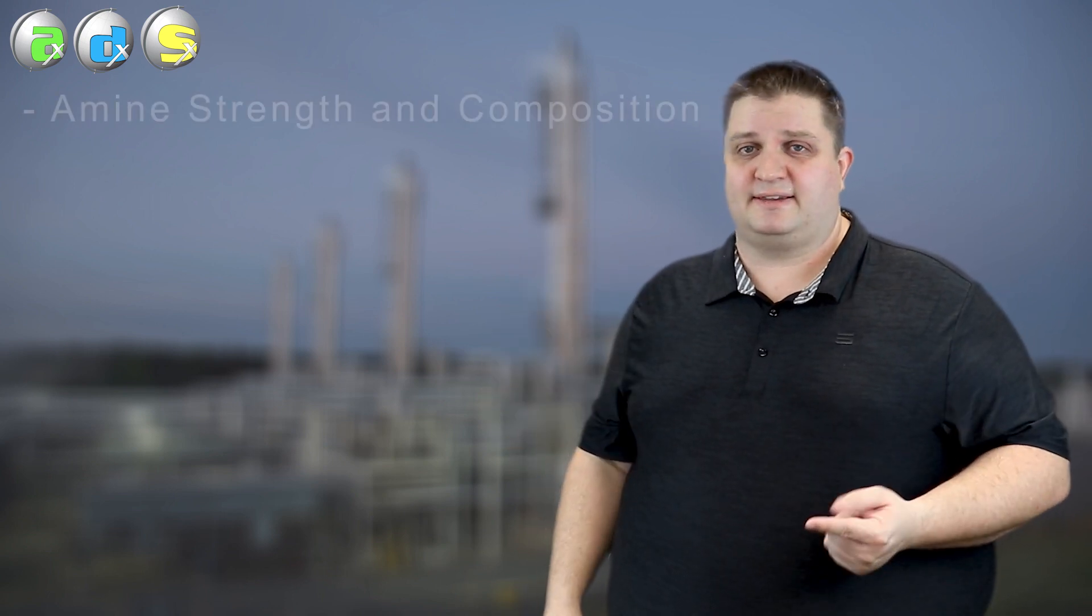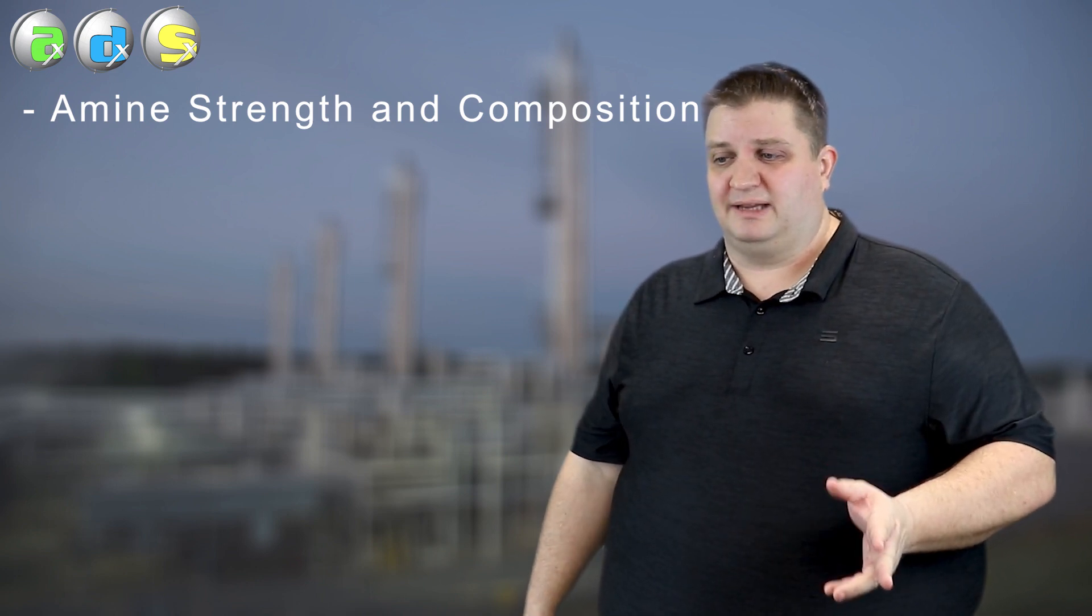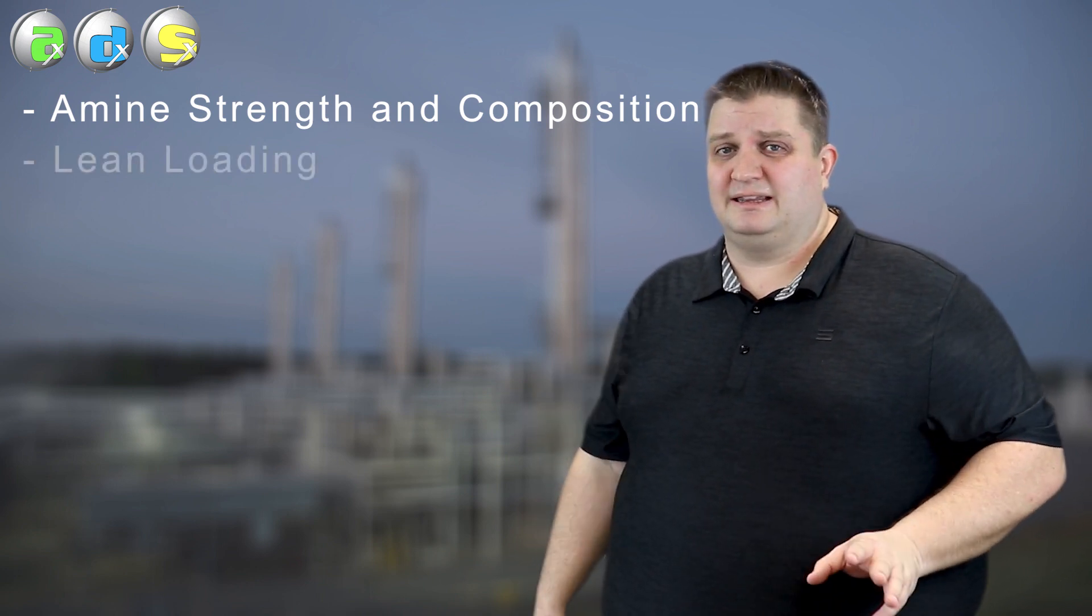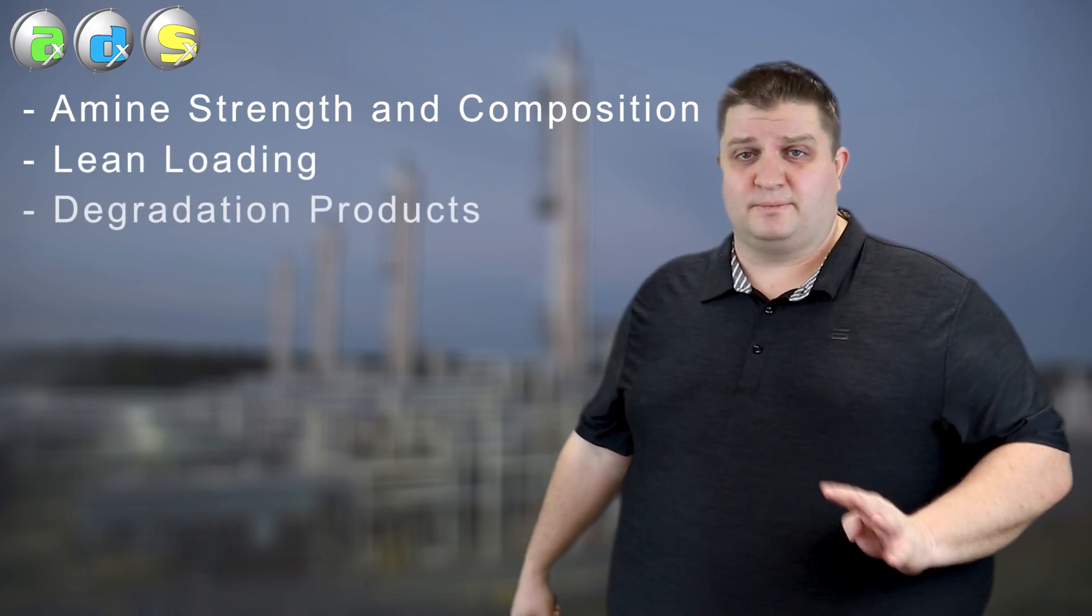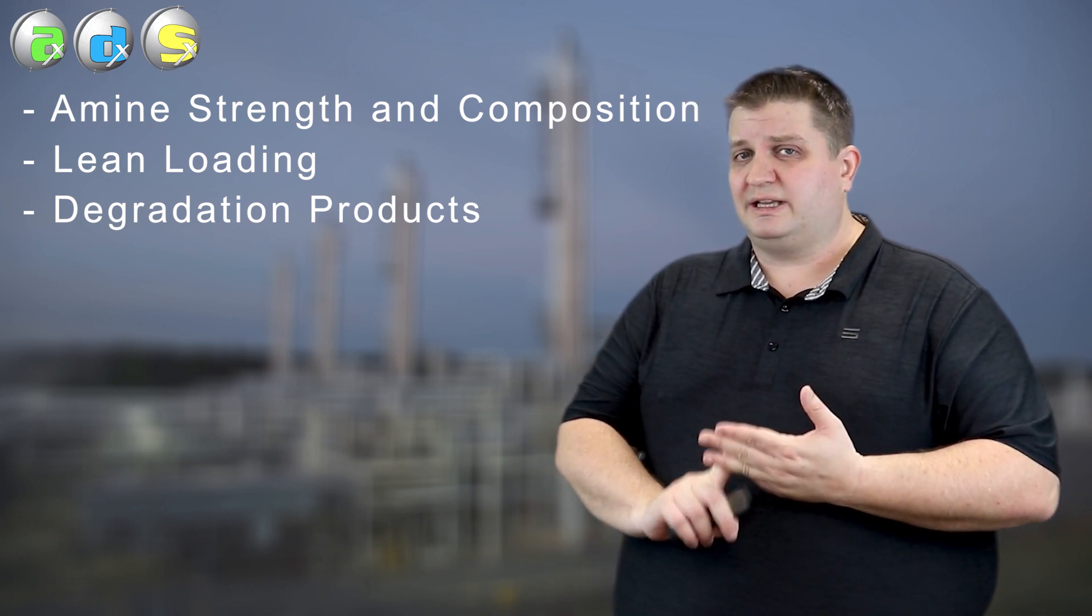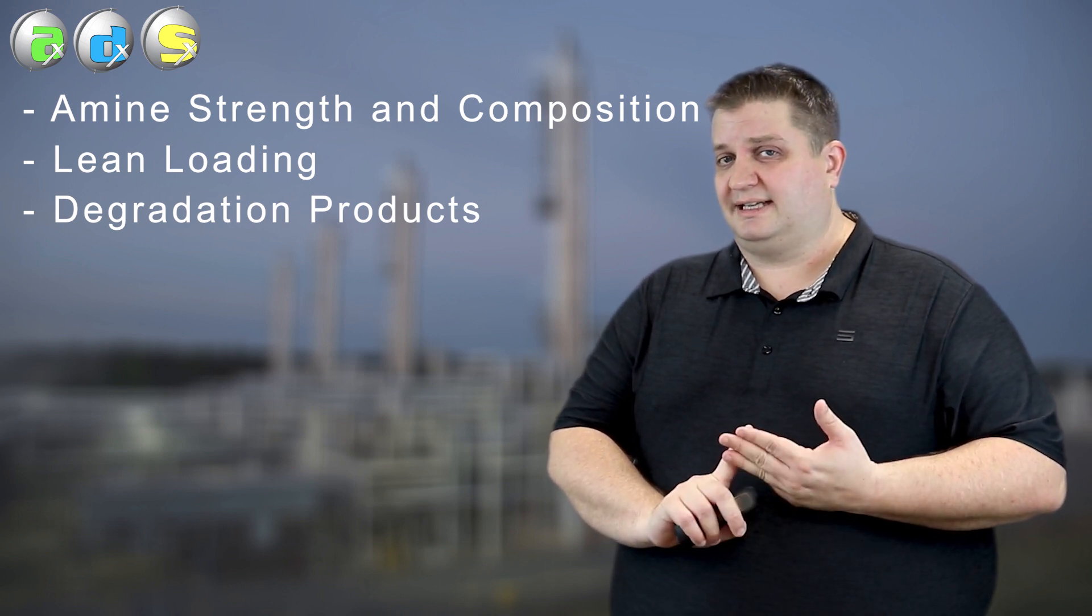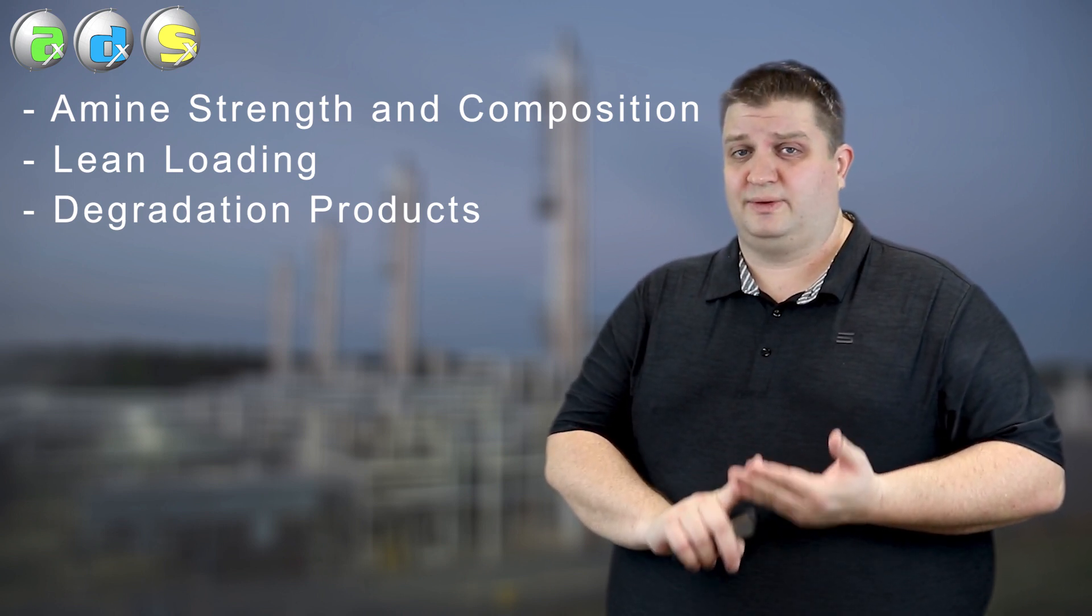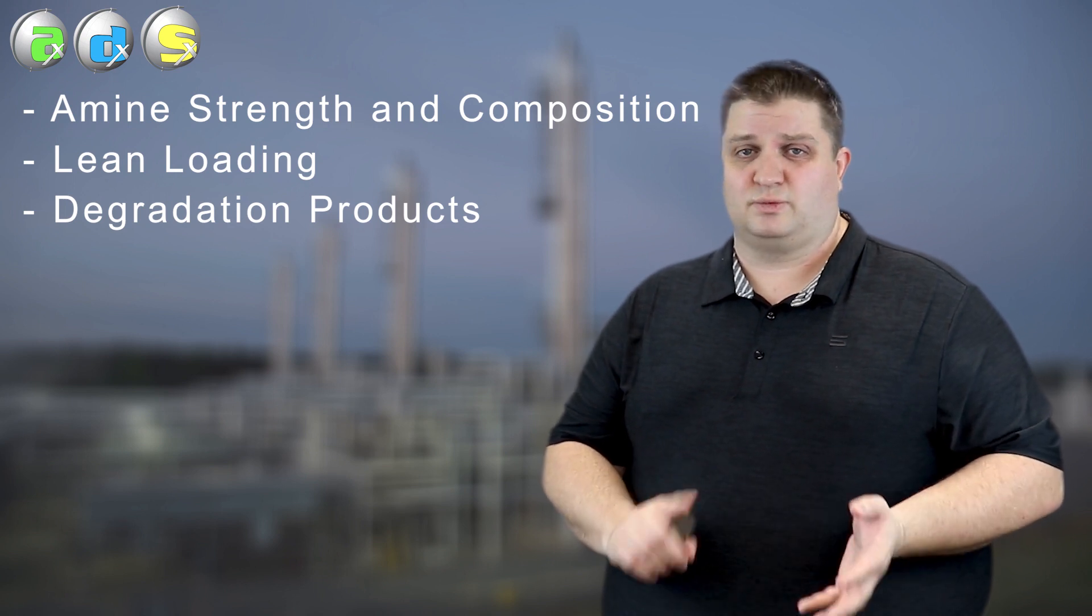When you send it to an off-site lab you're going to get a pile of information. They're going to give you a full accurate amine strength including the main amine you're using and any secondary amines that make up the blend. You're going to get a complete lean loading for both the H2S and CO2. You're going to get the degradation products. Are you getting other amines that shouldn't be there? Glycols that shouldn't be there? This is really important for an amine like DGA because it's also going to get you something like the BHEU which is the urea content and this is how you evaluate how well your reclaimer cycle is working in the system.